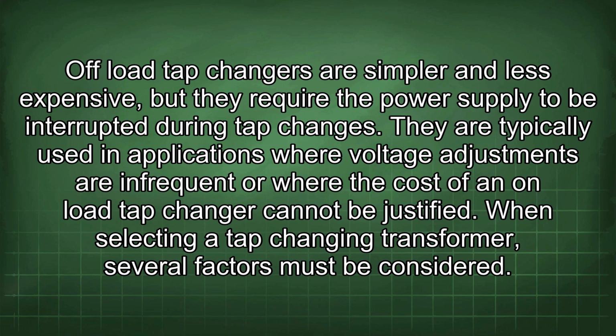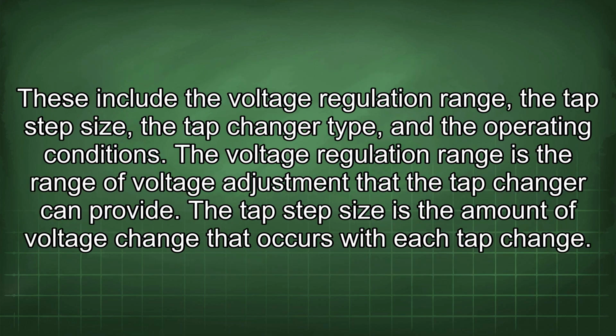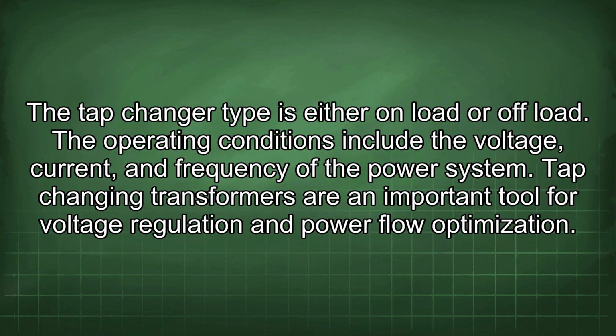When selecting a tap-changing transformer, several factors must be considered. These include the voltage regulation range, the tap step size, the tap changer type, and the operating conditions. The voltage regulation range is the range of voltage adjustment that the tap changer can provide. The tap step size is the amount of voltage change that occurs with each tap change. The tap changer type is either on-load or off-load. The operating conditions include the voltage, current, and frequency of the power system.